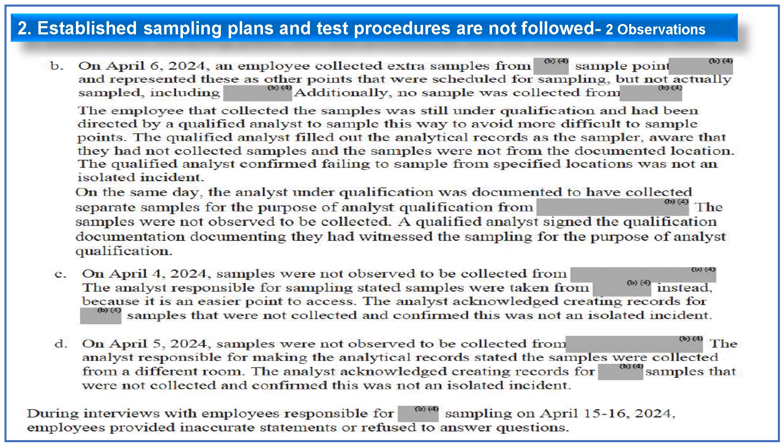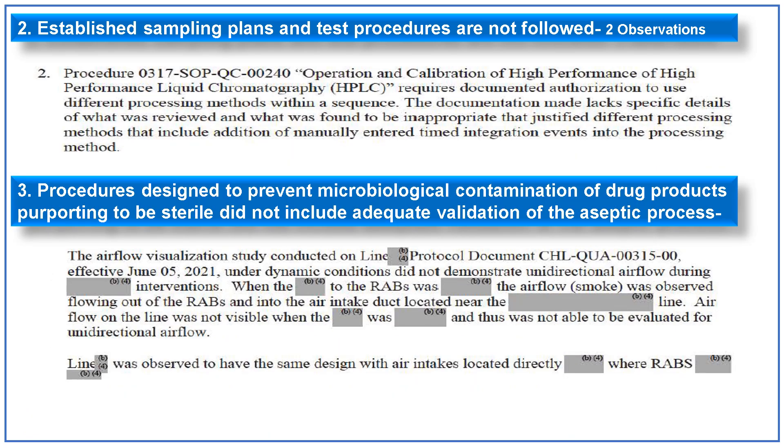During interviews with employees responsible for sampling during this time, they provided inaccurate statements or refused to answer questions. The second sub-point of the established sampling plan not followed relates to the procedure for operation and calibration of HPLC, which requires documented authorization to use different processing methods within a sequence. The documentation lacked specific details of what was reviewed and what was found inappropriate to justify different processing methods, including addition of manually entered timed integration events into the processing method.